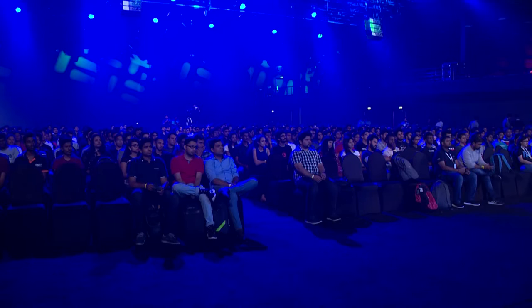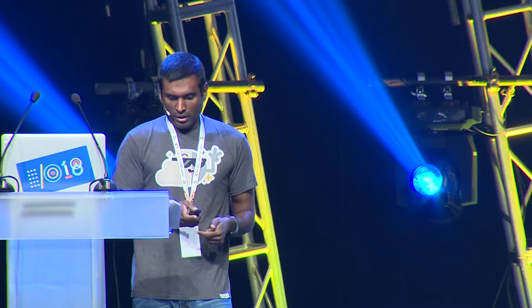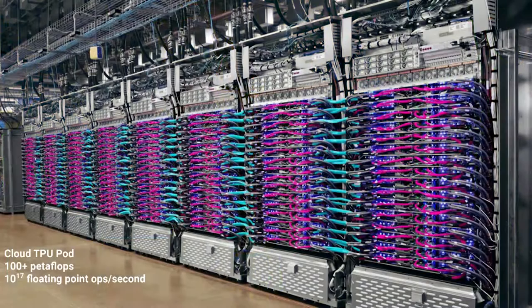Not all data center hardware is cheap and unreliable — there are also cool and unique specialized devices. Take the Tensor Processing Unit, or TPU, designed and developed by Google for our data centers. It's essentially a processor optimized for vector operations very common among machine learning applications. It heats up a lot, so copper tubes allow water to be injected directly into the processor housing to cool it from the inside. It's about the same size as a commercial graphics card, so those tubes are very narrow. We had to ensure the water fed to this device is absolutely pure with the exact pH value needed — any impurities would clog the tubes over time.